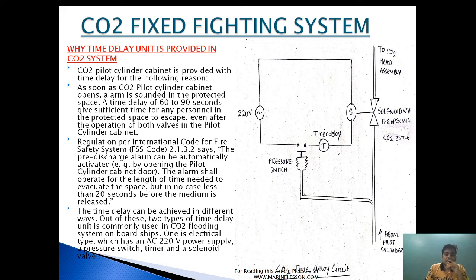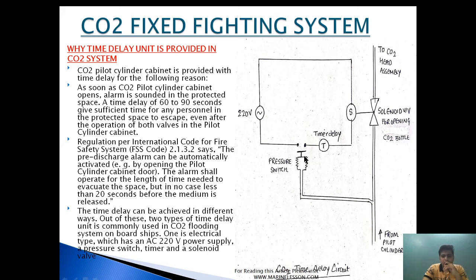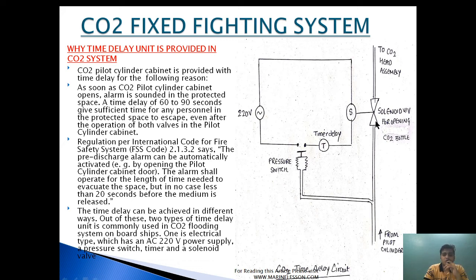A time delay of minimum 20 seconds is required, but as a safe side it is kept at 60 to 90 seconds. The CO2 from the pilot cylinder comes through and activates a pressure switch. Through a timer delay, the solenoid for the operation of the head assembly puncturing is determined. The pilot cylinder activates the pressure switch, and through the time delay the solenoid valve for opening the CO2 bottle is timed by this timer, which then goes to the CO2 head assembly.